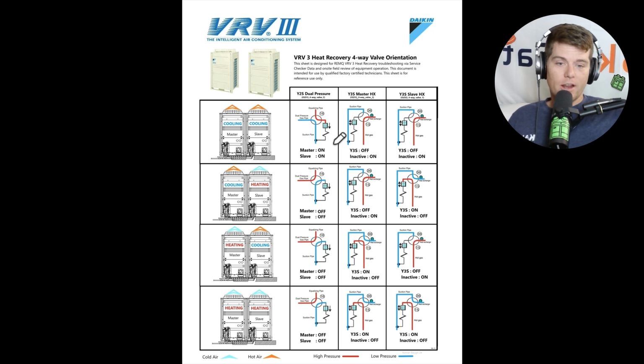This lets you understand what four-way valve positions they should be in. In cooling mode, your dual gas line should be on. In heating mode, your dual gas line should be off. There should be hot gas flowing into the building. I even gave you refrigerant piping diagrams that are colored. Watch out. And so this is all dual gas right here.